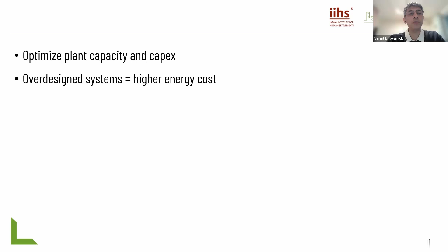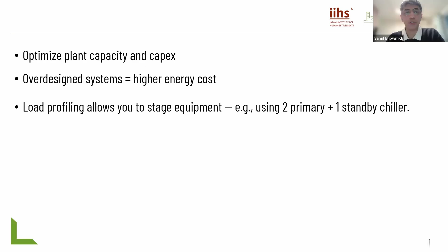Obviously, heavily oversized systems are not efficient, so they consume not just capex. You also end up with a higher opex with highly oversized systems. What load profiling also lets you do is stage equipment. For example, in the previous slide we saw 300 tons. So you could have two chillers of 300, or you could have 150 tons times three. All of these decisions you can take based on the load profile. So our strategy number one, and something absolutely essential, is to use the benefit of diversity to optimize equipment plant capacity. That's our strategy number one for today.